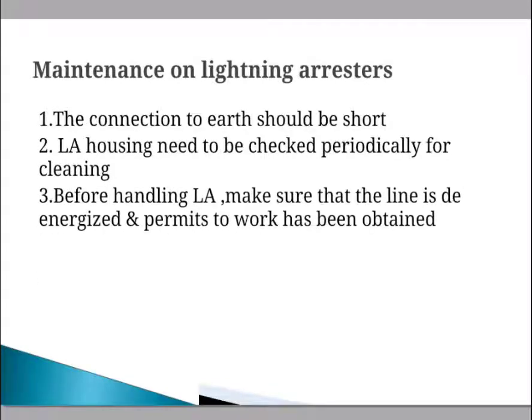For maintenance of the lightning arrester, we have to check that the connection to earth is secure. The lightning arrester housing needs to be checked periodically for cleaning — if dirt has accumulated, we must clean it. Before handling the lightning arrester, make sure the line is de-energized and a permit to work has been obtained from higher authorities.